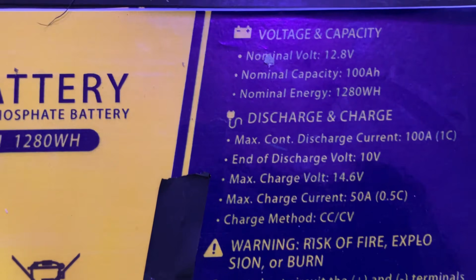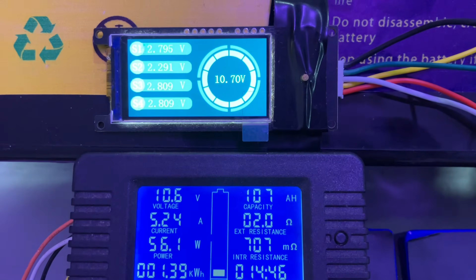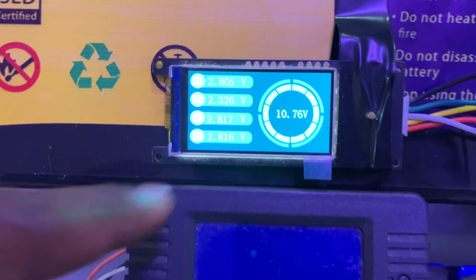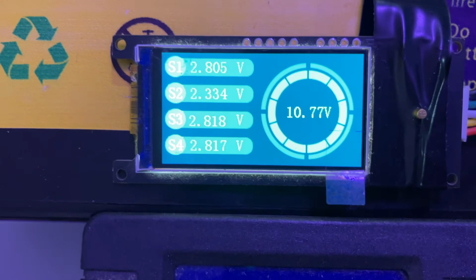Our battery is almost doing 1.4 kilowatts and is rated for 1.28 kilowatts. At 10.6 volts that cell went to 2.0 and shut down. The BMS shut down first, and you can see this cell has regained voltage. The BMS shut down at exactly 2.2 volts.